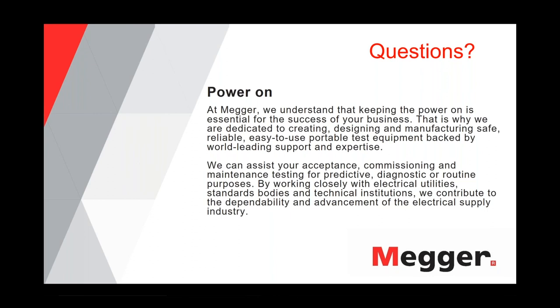All right, and the next question for you is, in transformers, we usually see guard rings used to collect the leakage current in the bushings. What about in the cables? Yeah. Well, theoretically, a tan delta measurement should always be done with guard rings, okay? From the theory, that is the best possible measurement you can do. But there are some practical considerations.